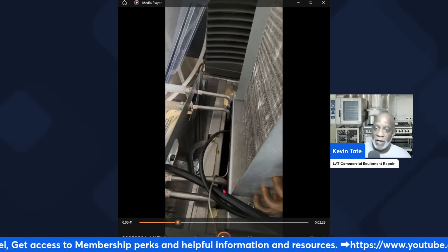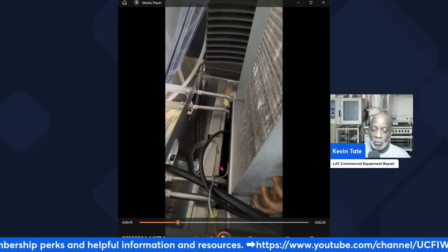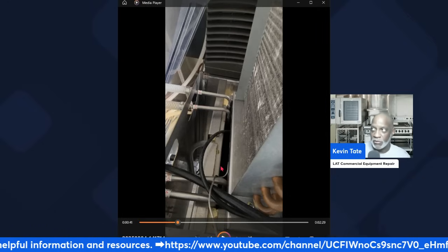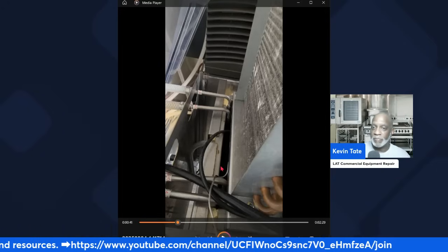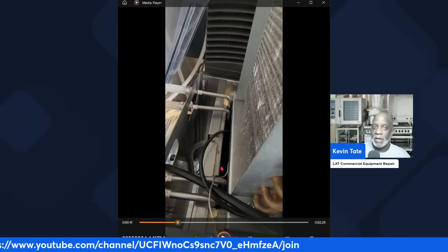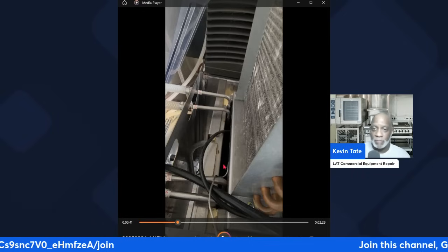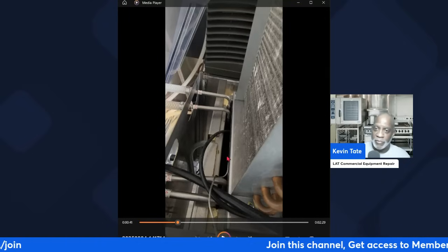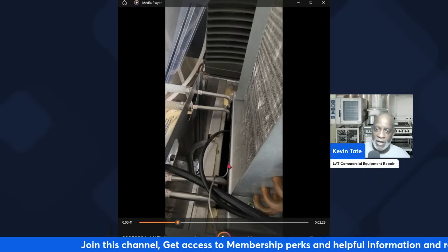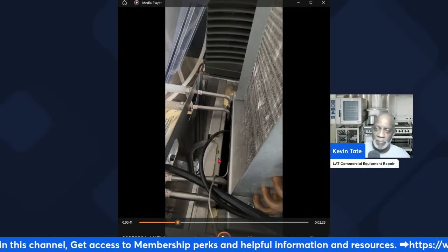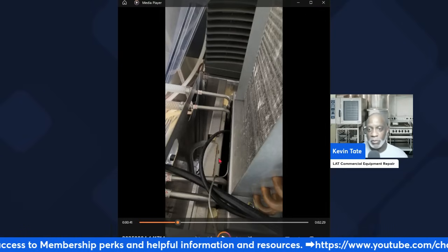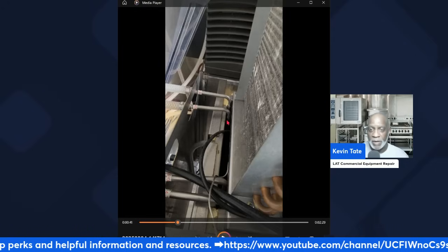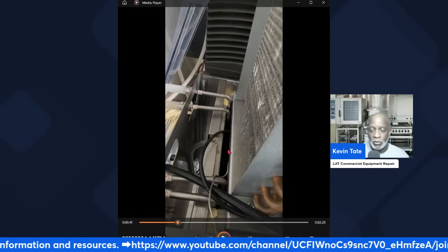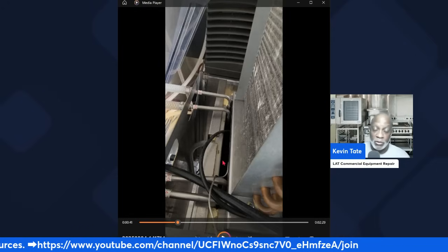That's a main thing to watch out for on these 500s. If you ever have a call of it not cooling, a good thing to do is take the top off, go to the back. There's an open space between where the condenser coil is and the machine itself, and you'll be able to see down in that opening. Use a flashlight and you'll be able to see if there's any water in there.